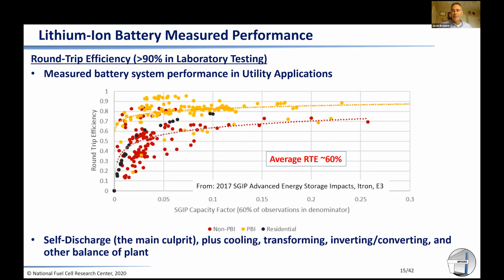Itron doesn't say, E3 doesn't say in this report, but we know what it is: self-discharge. Self-discharge is the main culprit leading to low round trip efficiency in battery utility applications. How do we know this? The clue is in this data, plotted against capacity factor.